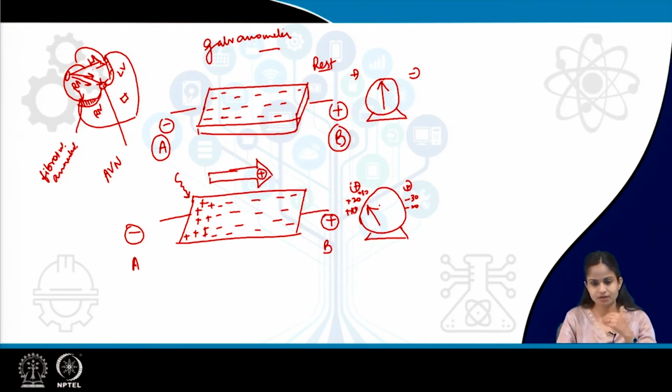In case of ECG, the way the paper rolls and the way the needle of the galvanometer moves are usually kept perpendicular to each other. So, that is why we get the deflection either upwards or downwards. The upward deflection is the positive deflection, and whenever the deflection is downward, any waves we get downwards, that is a negative deflection. So, in the second case what we have seen, whenever a depolarization wave is moving from point A to point B, that means towards the positive electrode, there is a positive deflection.